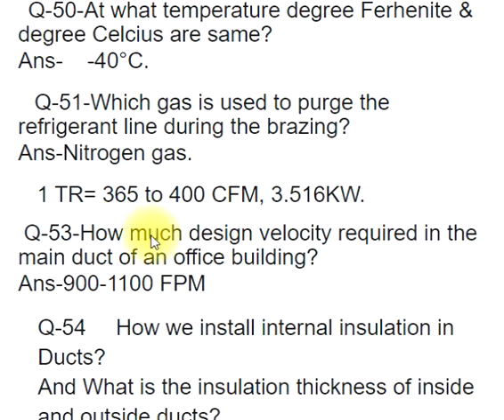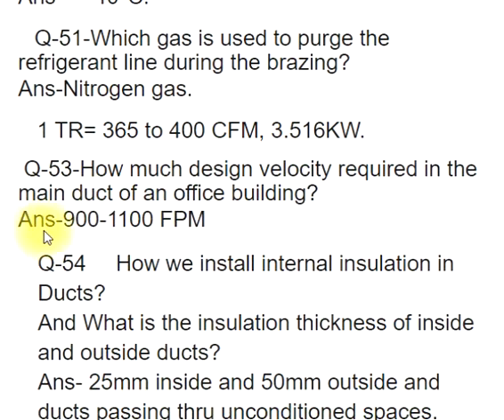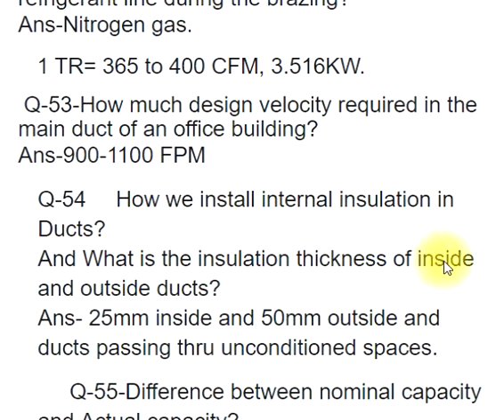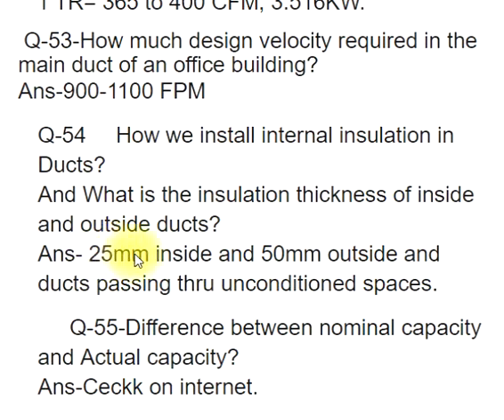Q53: How much design velocity is required in the main duct of an office building? ANS: 900–1100 FPM. Q54: How do we install internal insulation in ducts? What is the insulation thickness inside and outside? ANS: 25 mm inside and 50 mm outside for ducts passing through unconditioned spaces.